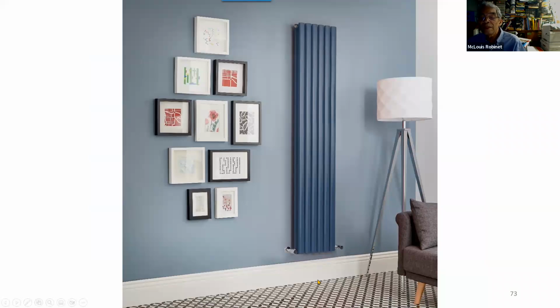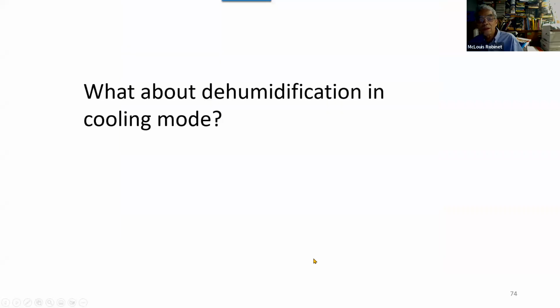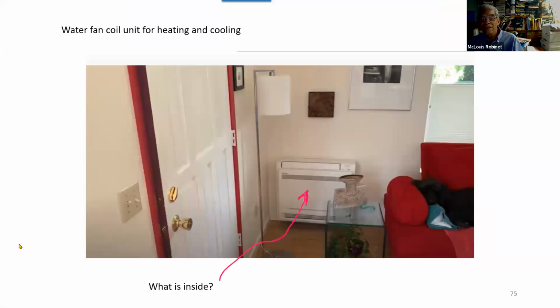But you have a heat pump that can provide both heating and cooling, so why not take advantage of it? You could provide cold water to these radiators, but as you know, there's moisture in the air. So after a while, this radiator will get wet and drip water on your floor. So you don't want to do that. Unless you're not interested in air conditioning, that would be a perfect solution.